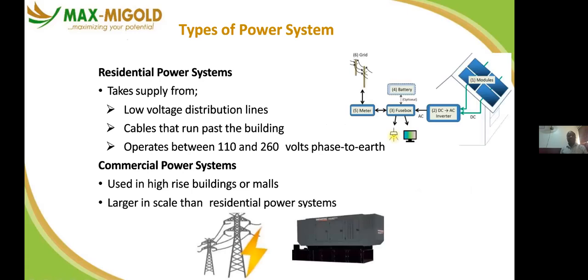So we have, as I said, the residential power system, which is the low voltage. It ranges from 110 to 240, as the case may be, based on the country that you are living in. So we have the low voltage distribution line. These are the wires you see on your streets. So they are mainly between 110 and 260. Here in Nigeria, we use between 110 and 240, phase to earth.